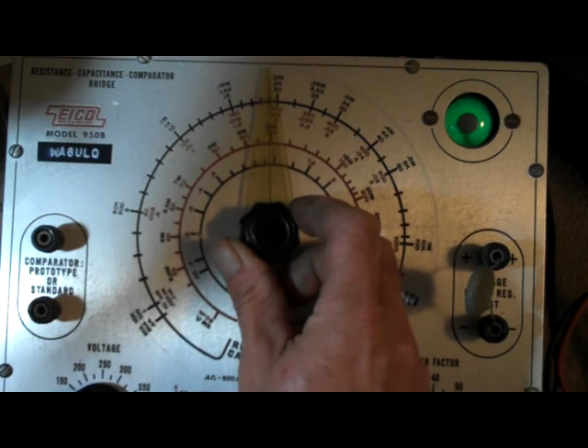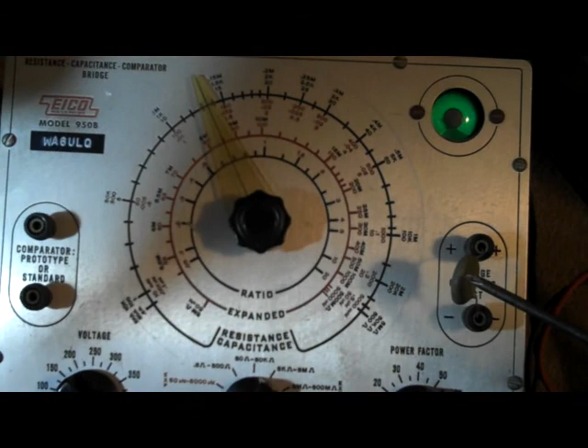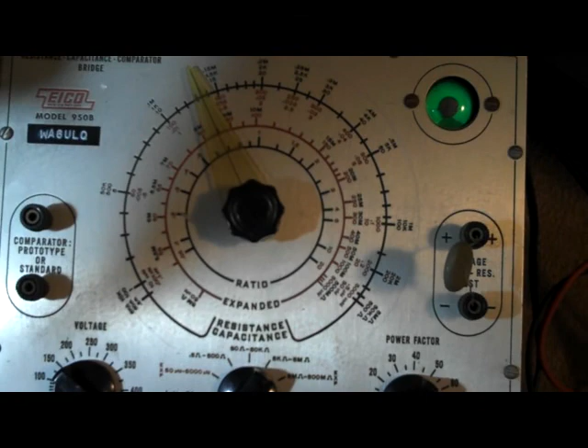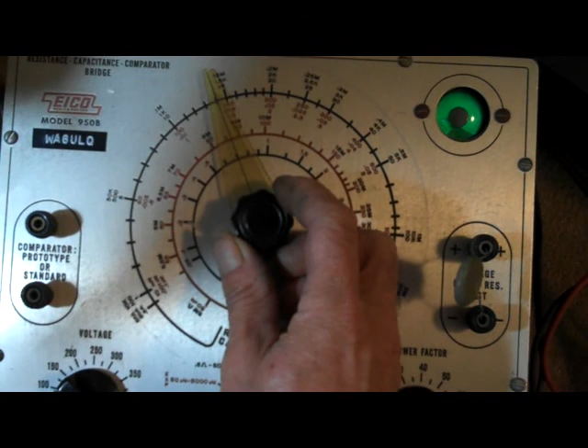So I have the replacement TDK 130 picofarad capacitor hooked up to the cap tester here, and you can see we get a definite eye right there, definite eye opening right at 130 picofarads, so that looks really good. I have the capacitor right here on the unit itself without the test leads. That's the best way to check these small values. Go ahead and install it and see if it makes any difference.